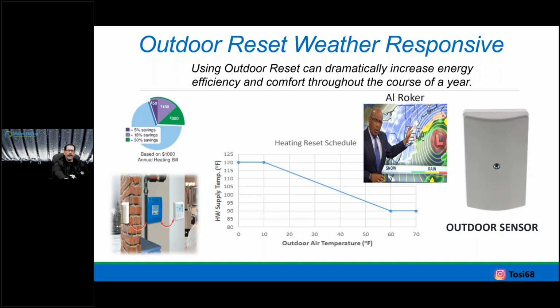You know, the other side of it is that when you hear a boiler, now it's funny, when I go out of non-condensing, right, I call it a boiler. When it's in condensing, I go to a heat engine or something like that, or high efficient. It short cycles. It's just grossly oversized, right? The heat can't leave the building quick enough. Comes back warmer, satisfies the boiler. And that's where we get in trouble.